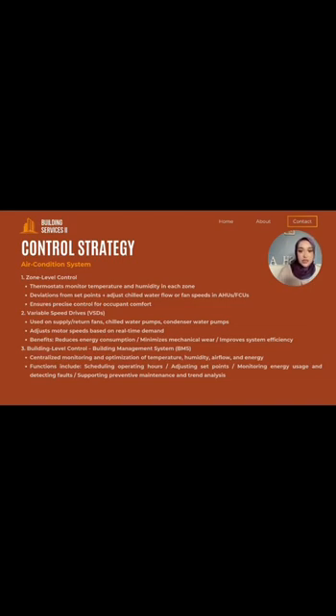Next is building level control, which is used in the building management system (BMS). It will centralize monitoring and optimization of temperature, humidity, airflow, and energy.